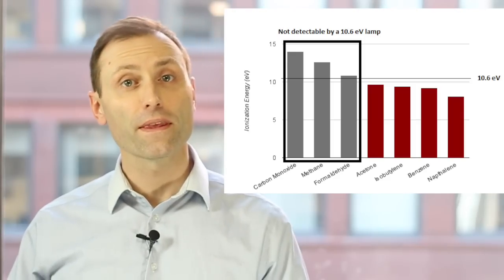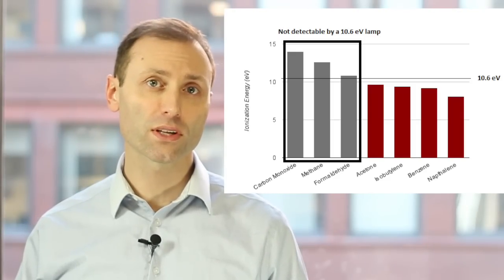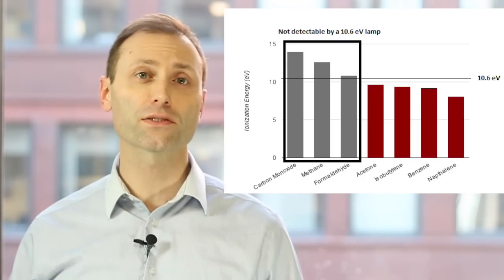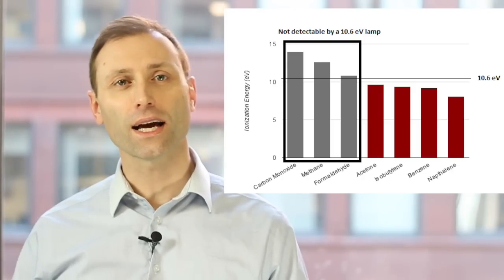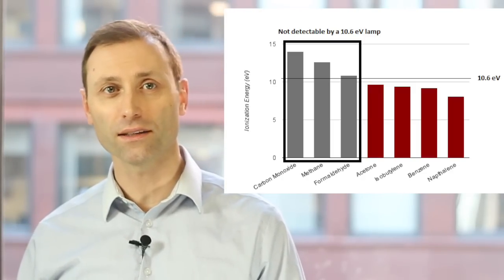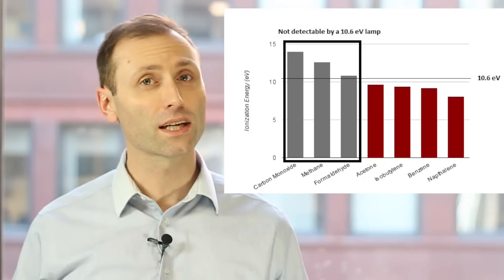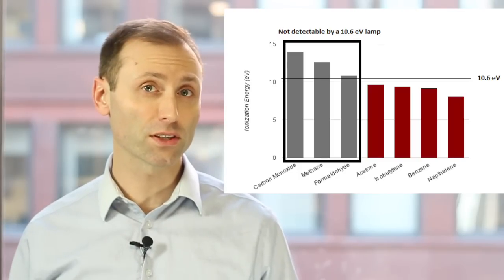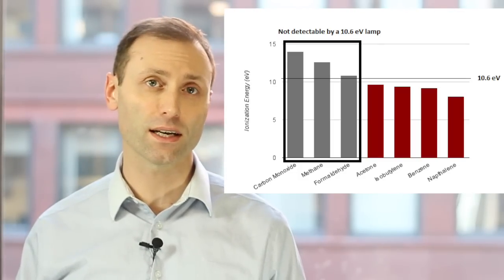For example, if the PID has a 10.6 electron volt lamp, it won't have enough energy to ionize formaldehyde, which has an ionization energy of 10.9. Put another way, a 10.6 electron volt lamp will be blind to formaldehyde, not to mention methane and carbon monoxide.